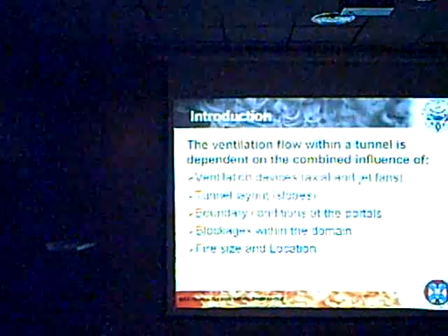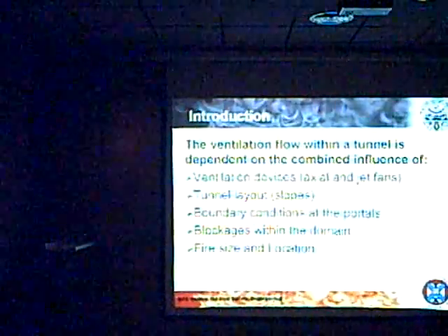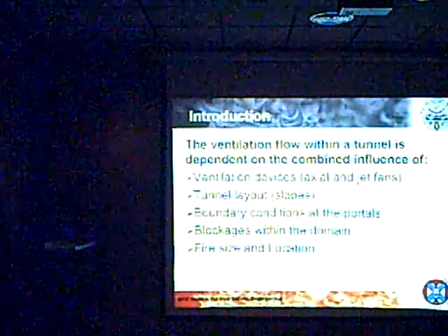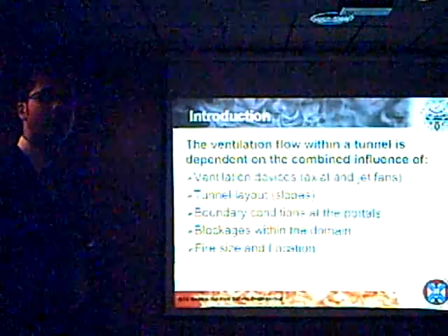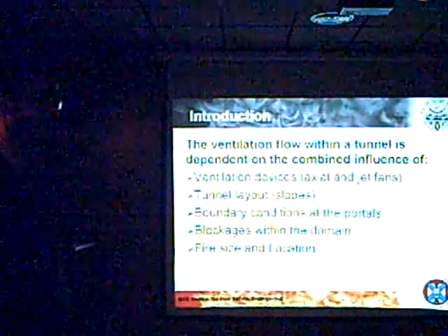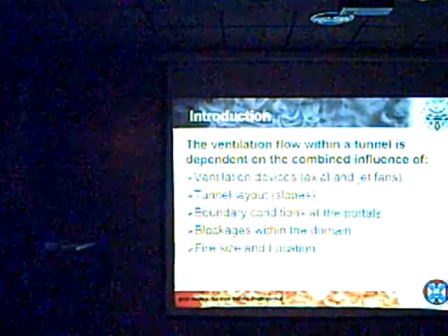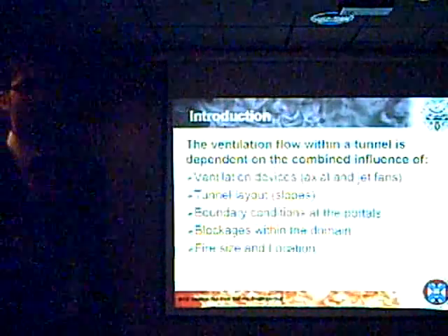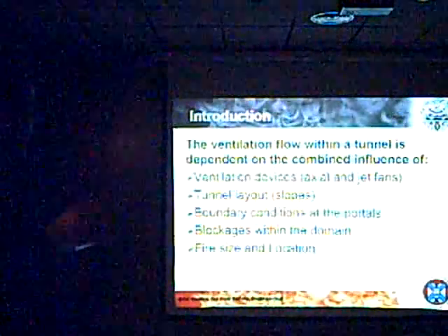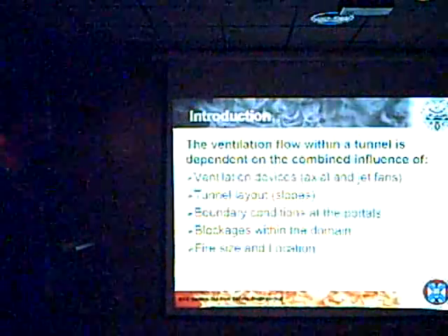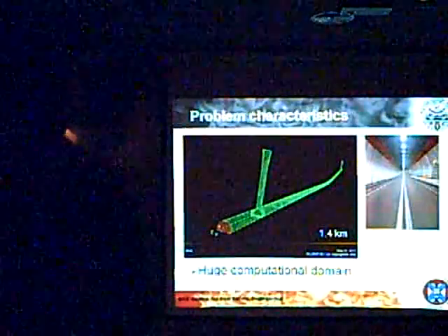So the ventilation flow within a tunnel is dependent on the combined influence of many parameters. First of all, for sure, the ventilation devices, so the number of fans and their power. Also the tunnel layout affects the final ventilation flow, with the geometry, the presence of slope, eventually the friction coefficient, the presence of shaft. The boundary conditions at the portal, so wind, pressure on both the portals and also on the top of the chimney. Also, the presence of blockages within the domain affects the final ventilation flow, as well as the fire size and location.